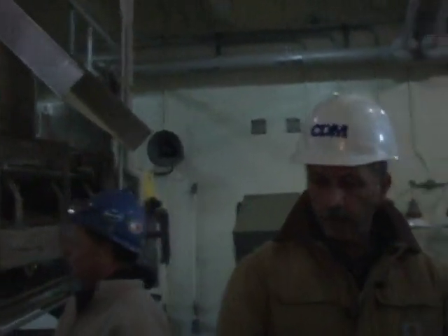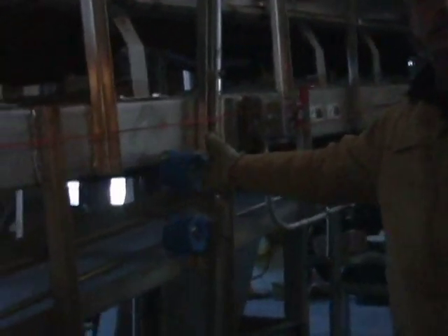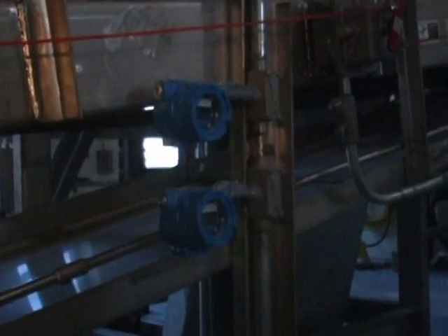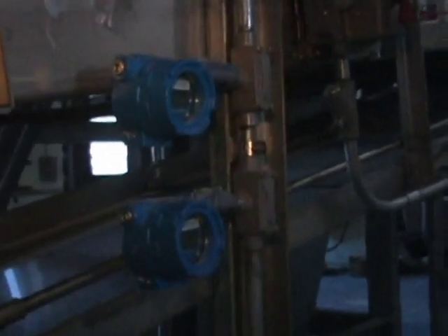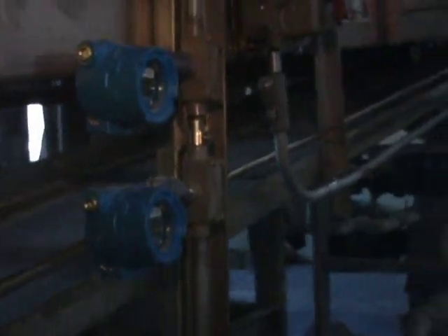Okay, on the downstream side of the screens within the channel, there's also a level measuring device located directly below this plate in the floor, similar to what you saw on the upstream side. Those readings are read out here. They're currently marked with a piece of duct tape with an instrument number on it. They will be tagged so you can identify which one is which. That's looking at the level of the water within the channel itself, again monitoring for your high-level differential across the screen in order to bring the screen on if needed.